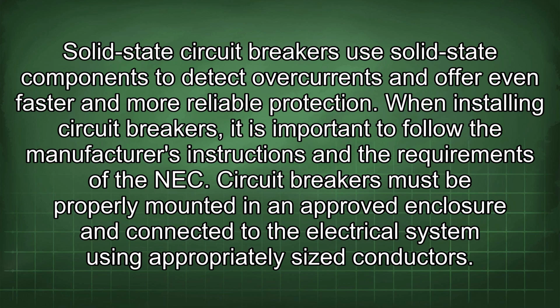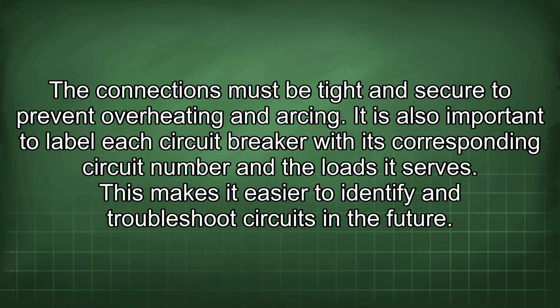When installing circuit breakers, it is important to follow the manufacturer's instructions and the requirements of the NEC. Circuit breakers must be properly mounted in an approved enclosure and connected to the electrical system using appropriately sized conductors. The connections must be tight and secure to prevent overheating and arcing. It is also important to label each circuit breaker with its corresponding circuit number and the loads it serves. This makes it easier to identify and troubleshoot circuits in the future.